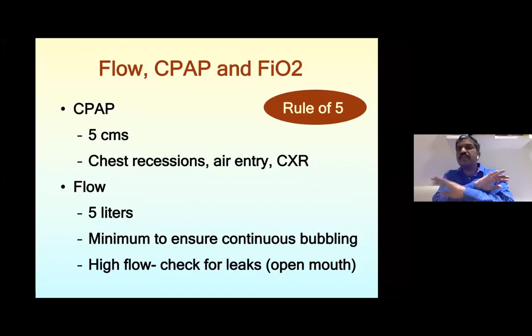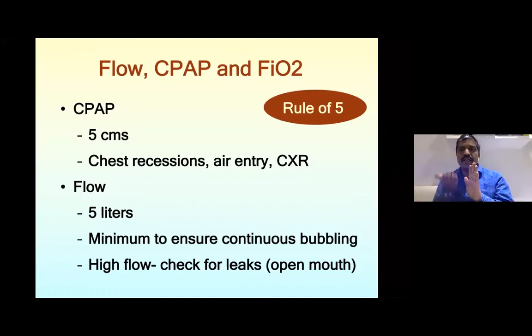Still no bubbles, that means there is definitely a leak in the circuit. If you are not getting bubbles with 7 liters flow, there's something wrong in the circuit. You should get bubbles with 7 liters flow for all the babies. Start with 5. Most of the time 5 is sufficient, but bubbles should be there. If no bubbles, look for leaks. If no leaks, increase the pressure of flow from 5 to 6, 6 to 7.